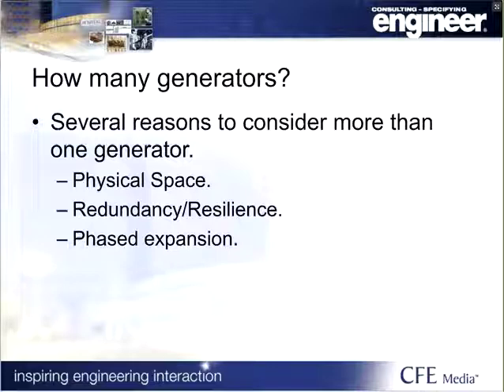One thing to consider when selecting your generator rating is the loading at both peak and low times. If you anticipate this to vary greatly, you may run the risk of underloading the generator. Over time, this could cause serious performance issues and damage the generator. Generally, you do not want to load the generator to any lower than 30% of the nameplate rating. So if, for example, the full capacity required for a phased build-out of a new property is being installed up front, choosing multiple generators will allow the system to operate more efficiently by shutting down some generators if the load does not demand the full aggregate capacity of generation.